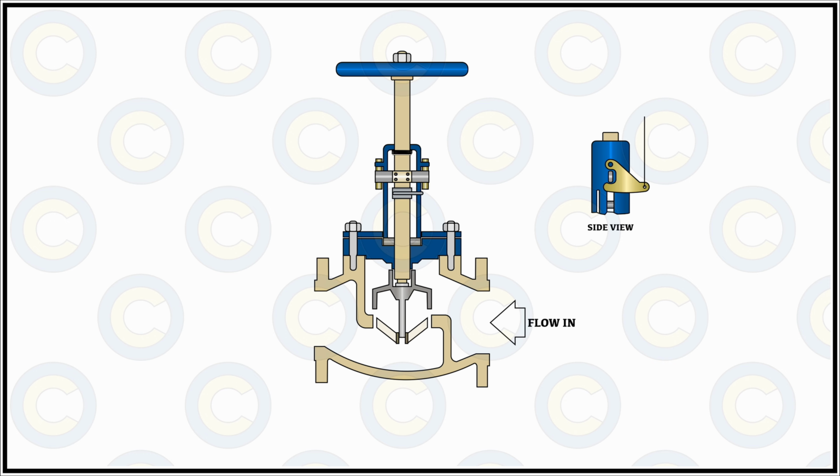Why? Because it helps us in resetting the spring and the spindle mechanism by pushing it to the maximum length down, and thus making sure that first of all the valve manually is in its fully closed position, and then once everything is in order and the entire free length of the spring is extended and the retaining disc, that is the locking part or the locking needle, is also in its original position, then we start opening this valve and retain it back to its original position.